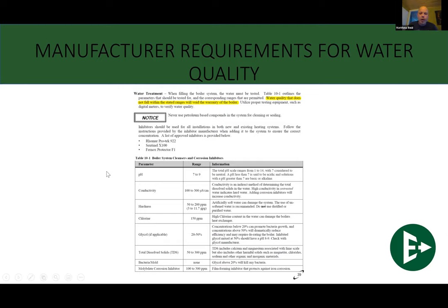Now, this is a manufacturer's instruction. This is a water quality level that is required by a manufacturer. I'm pretty sure that this one is Viessmann. And if we look down here, it's looking for a total dissolved solids between 50 and 300. It knows that anything above that, we're talking about way too much scale that can possibly happen in the system. And anything too far lower than that, and you can be talking about creating some hungry water. Although you can go down to about 20 to 30 and still have absolutely no problems. But boiler or manufacturer rules trump everything.